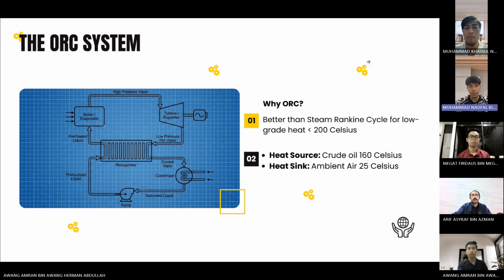So instead of SRC, why do we use ORC? Steam Rankine Cycle requires a more massive heat source. Since our heat source is only 160 Celsius, we use an organic fluid like refrigerant because it boils at a much lower temperature than water. The efficiency for the ORC system is high because this fluid has a higher molecular weight, which allows the turbine to extract more work even at this lower temperature.